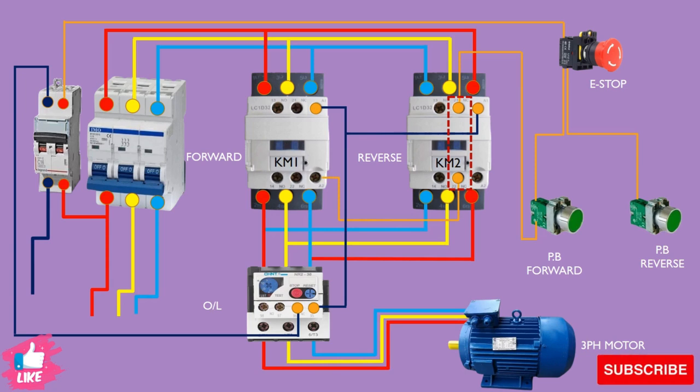When you push the forward push button, the power passes through the normally-close point of the reverse contactor and goes to coil A2 of the forward contactor KM1. When KM1 energizes, its interlocking normally-close point on KM2's circuit will go open. If you then push reverse it will not pass power from there. This system is called the interlocking system.